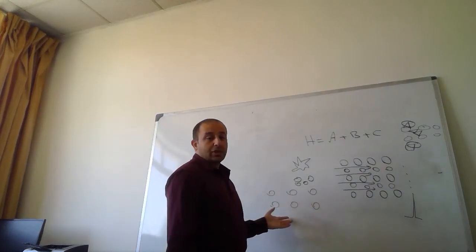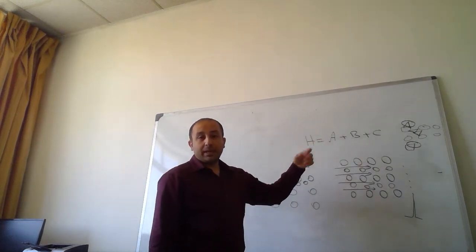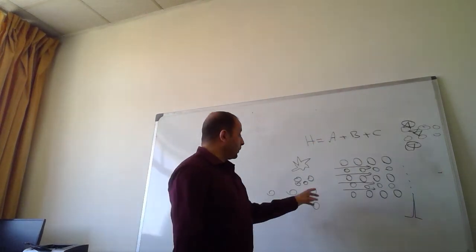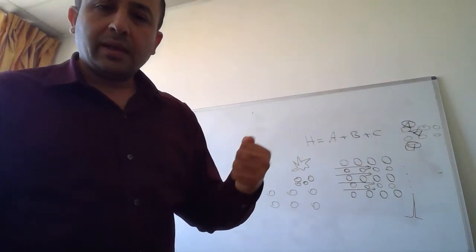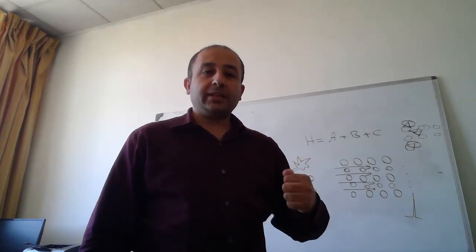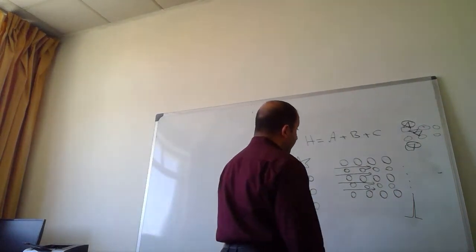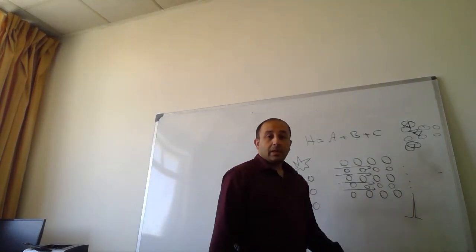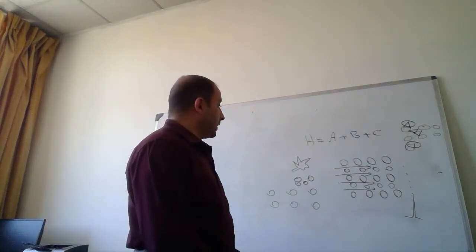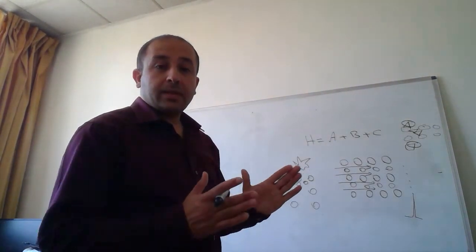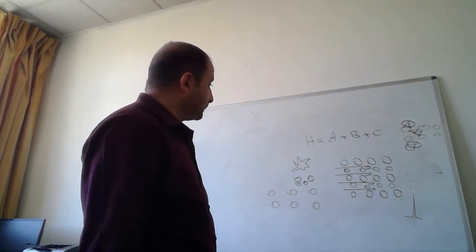So this will increase the peak broadening due to the multipath effect. To get them well packed, you have to apply very high pressure on the silica when you fill certain columns, and this is done by the manufacturer. They use very high pressure in order to get the bed similar in each section of the column.